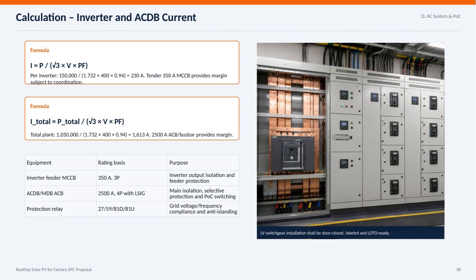Now, looking at the entire plant with a total capacity of 1,050,000 watts, we apply the same formula. This results in a total current of 1,613 amps. Hence, a 2,500 amp AC circuit breaker or busbar is selected, again offering sufficient margin. The table highlights the equipment and their ratings.